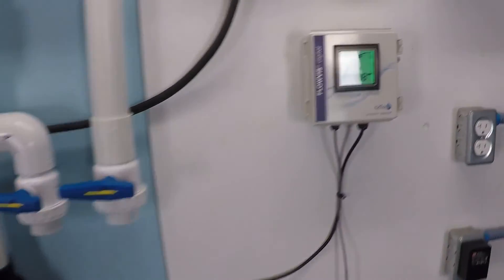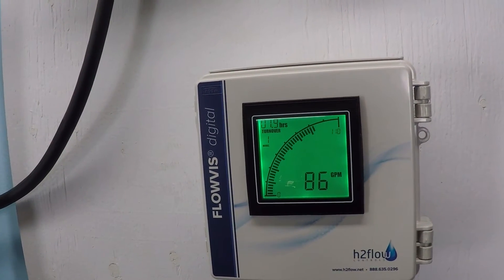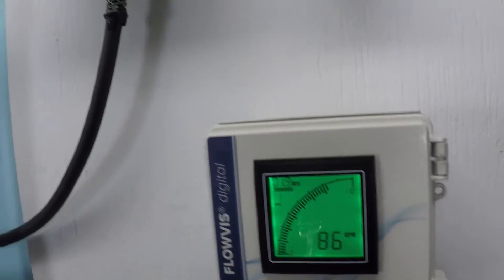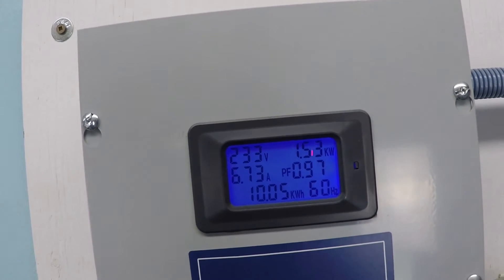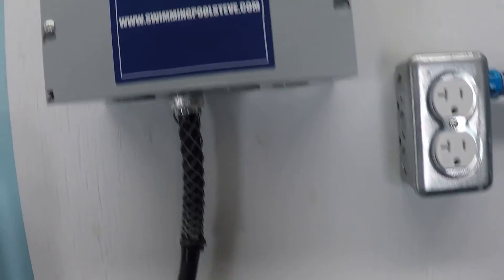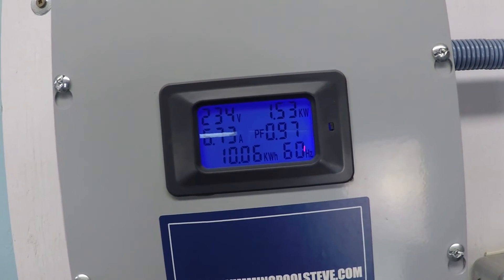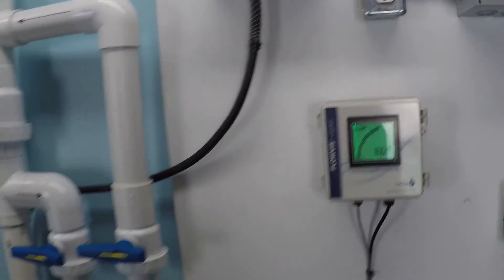First of all, it's a lot quieter at 3,000 versus 3,450. We lost about 15 to 16 gallons per minute, but we've dropped down to only 1.53 kilowatts. So we've dropped down a small amount in total flow, but quite a bit in the amount of power being consumed. You can see the real-time draw of amperage on the left at 6.7 amps for this pump at 86 gallons per minute.